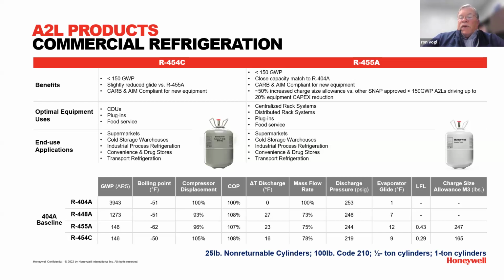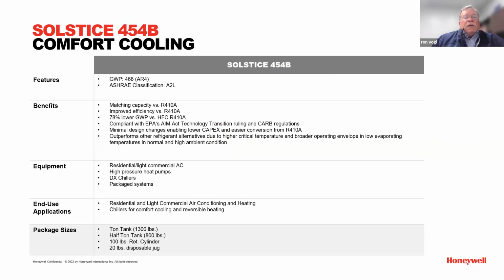But really, LFLs are there. You can see a difference between 455 and 454C. That's why you get a charge size difference. But pretty much every application where you use 404, the rest of it, you're going to see these 2 or 3 refrigerants find a home. 454B, I'll just go right past this. This is going to be Honeywell's main offering. We do not sell straight 32. I know Johnstone handles both 454B and 32, but we will supply 454B in 20-pound cylinders, a little different than the refrigeration, 100 pounds, half-ton tanks, ton tanks, etc.